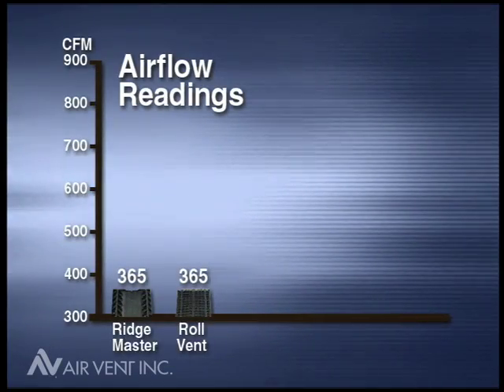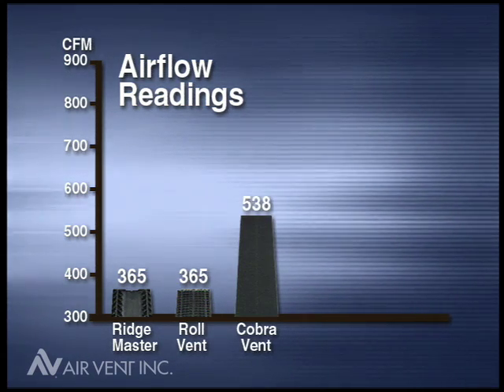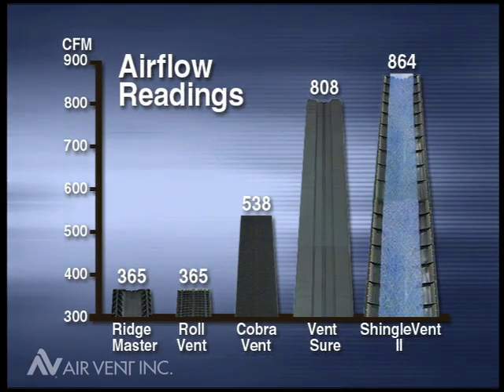Ridge Master and Roll Vent each allowed 365 cubic feet per minute of air to pass through. Cobra Vent, 538 CFM. Vent Sure, 808. And Shingle Vent II allowed 864 cubic feet of air per minute.